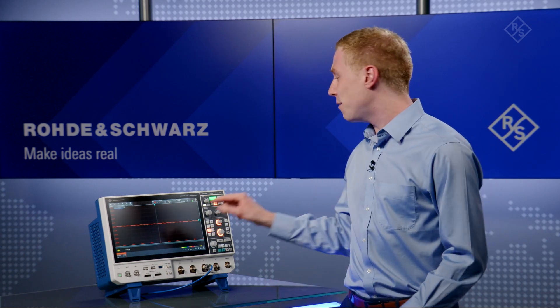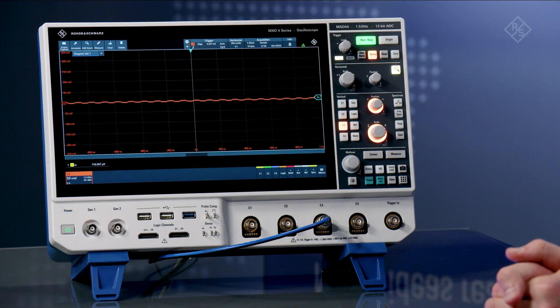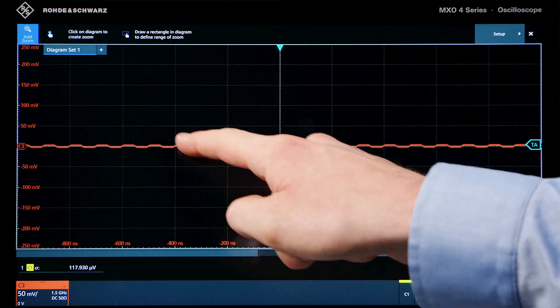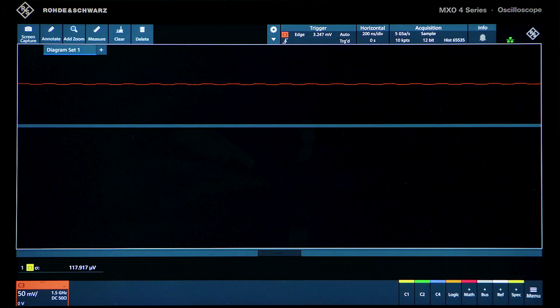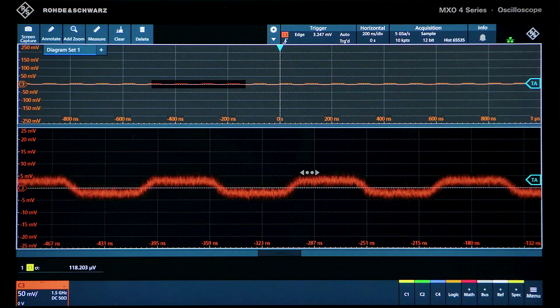In this scale you can see this is a very, very tiny signal. Let's add a zoom to see more detail. This looks like a square wave with an amplitude of around 10 millivolts peak-to-peak. The low noise architecture of the MXO 4 helps us to distinguish and characterize this noise accurately.